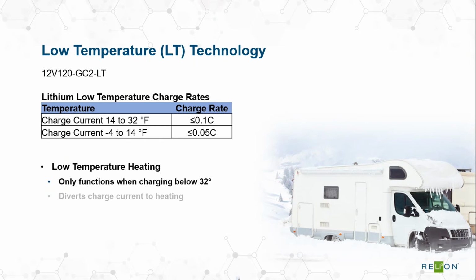This is why we developed our low temperature heating functionality in both our legacy and Insight batteries. I want to clarify it only functions when the battery detects a charge current and is below 32 degrees. The battery is equipped with an internal heating mechanism, and that charge current is diverted to heating until the battery reaches a safe internal charging temperature.